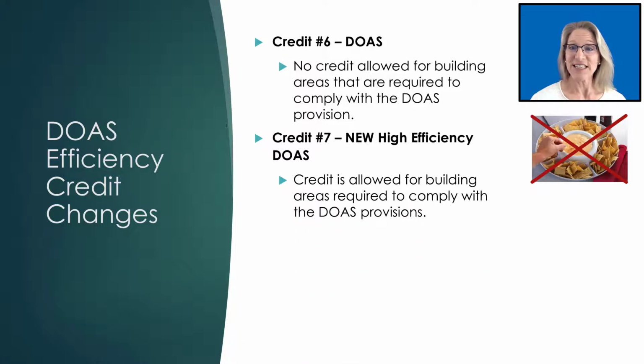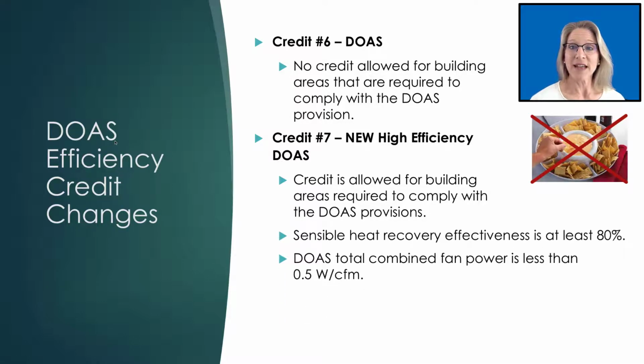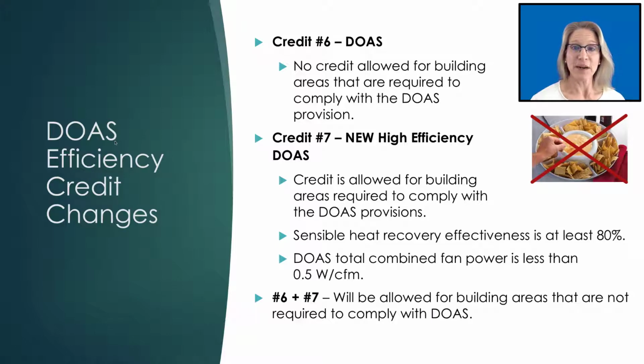The other change is there is now a new high efficiency DOAS credit. So those qualifying systems are required to have at least 80% sensible heat recovery effectiveness, and the fan efficiency must be less than 0.5 watts per CFM. Note that for those spaces that are not required to comply with DOAS, if you install a DOAS system and it is a high efficiency DOAS system, then you can apply both credits.